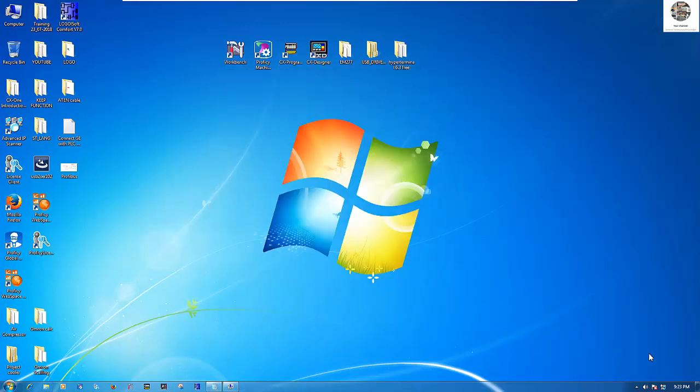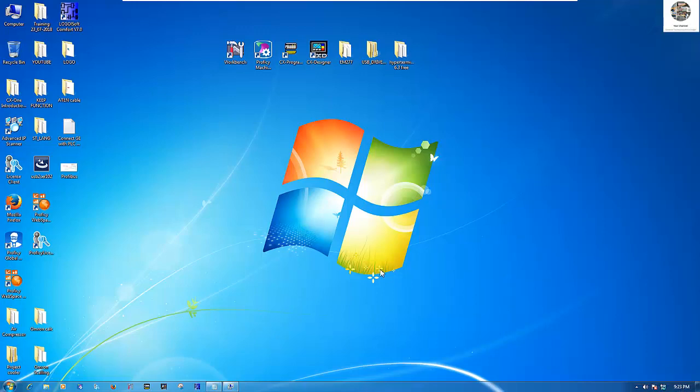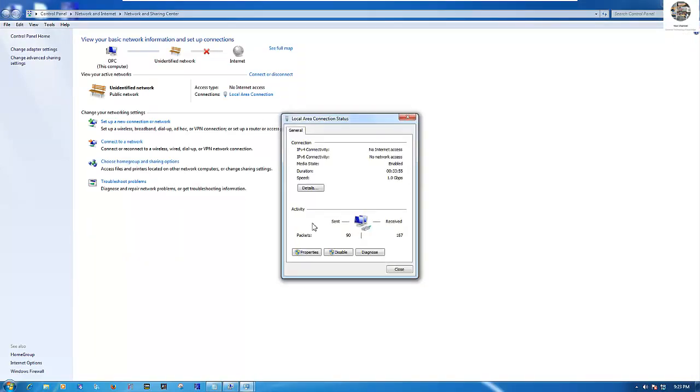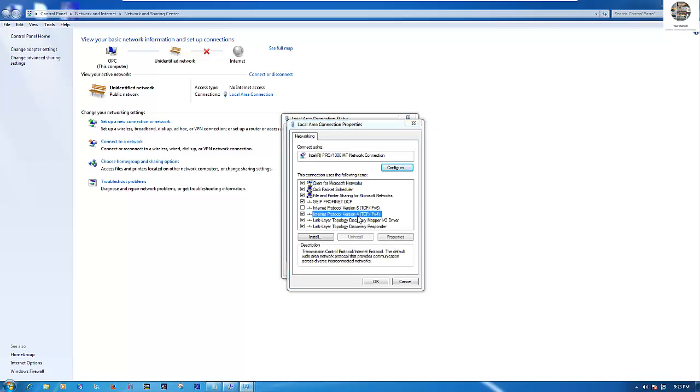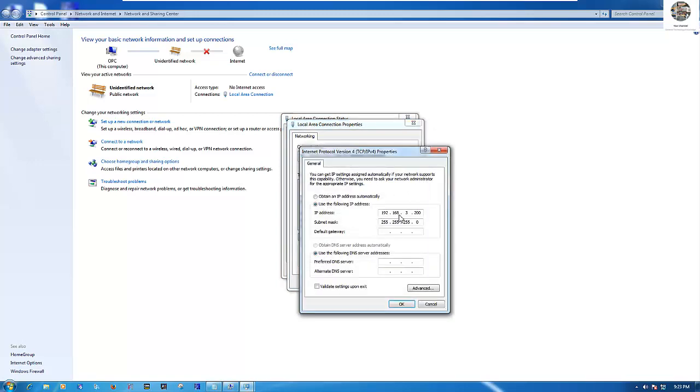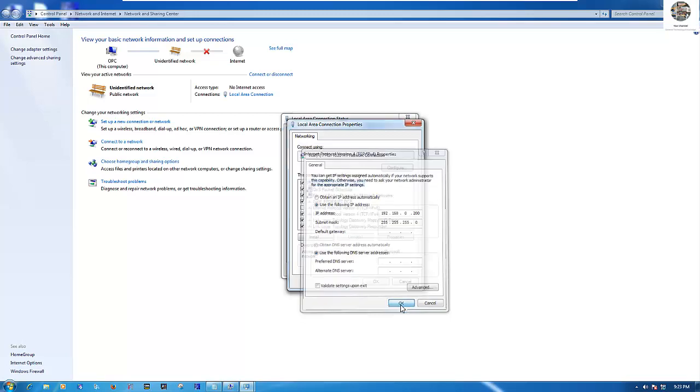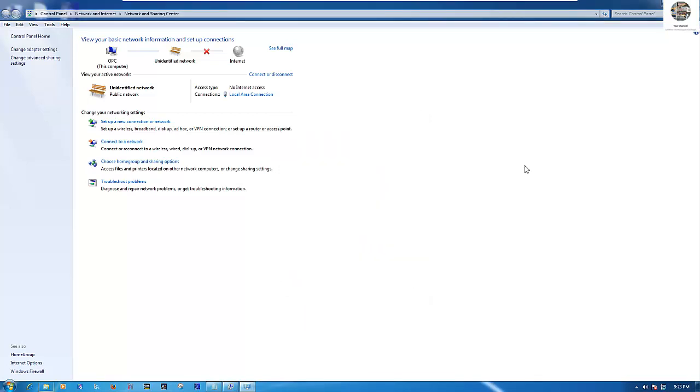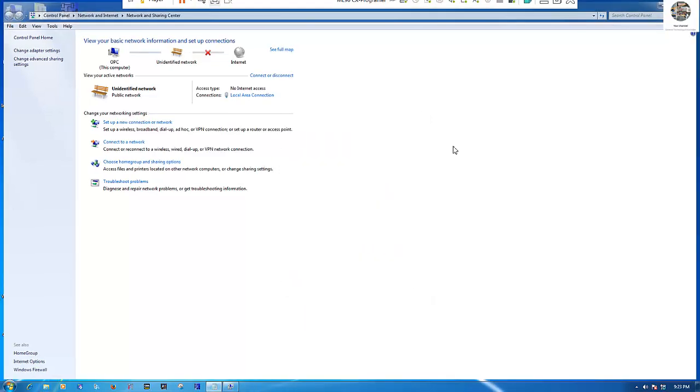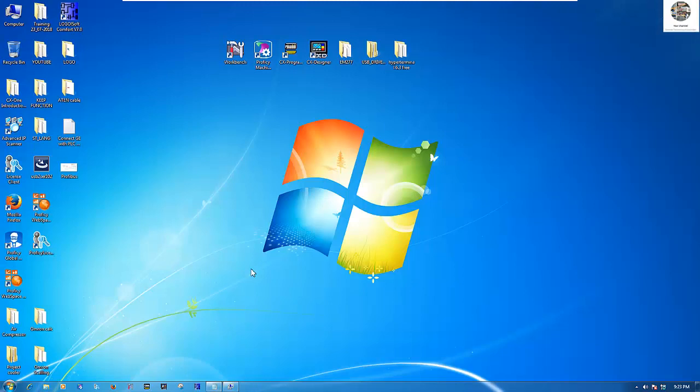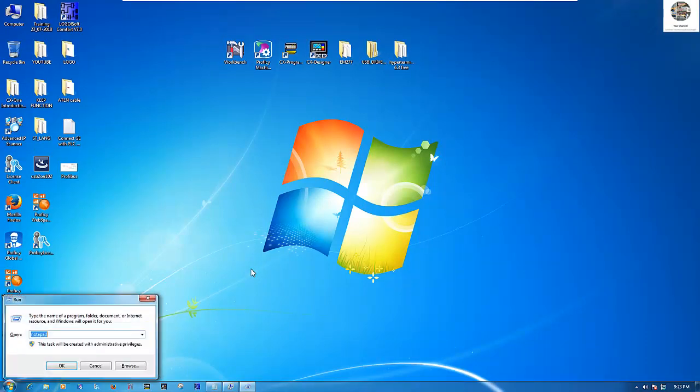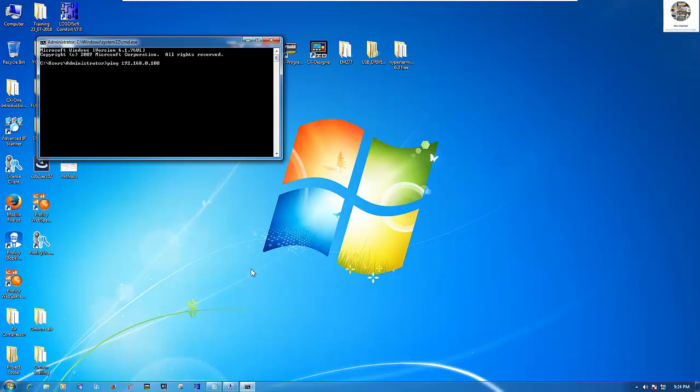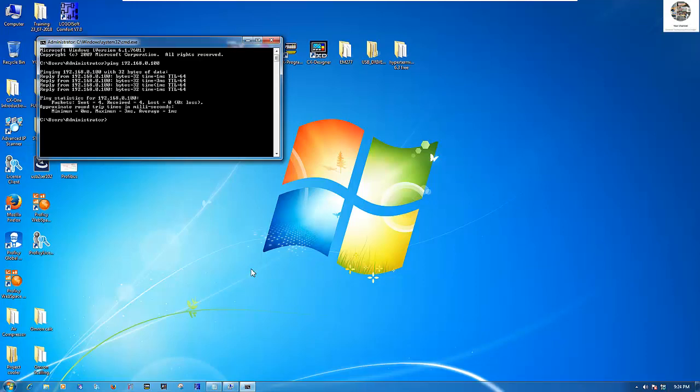And then we close it. So first we go to manually set our IP address of our computer. I set .0 because our module is .0 also. So let me ping. CMD ping. The new IP is 192.168.0.100. Right now it can ping from our computer to PLC GE module.